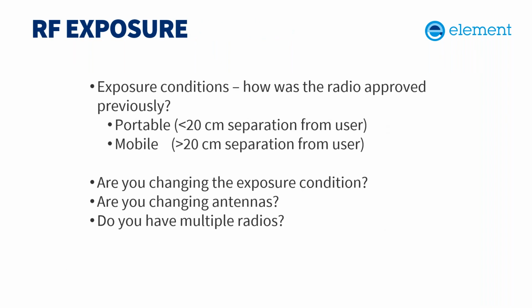Okay, so you also need to meet RF exposure requirements for the host with the radio in all markets. So a reminder that RF exposure can mean SAR testing, EMF testing, or calculation, but the requirements when integrating an off-the-shelf radio depend on what was done previously with that radio. So the FCC separates it into portable, mobile, and fixed, with portable being a product that's going to be less than 20 centimeters from the user. Classic example is a cell phone. And mobile is greater than 20 centimeters from a user. So an infusion pump, diagnostic cart, something like that, that's not directly next to a user in typical use.